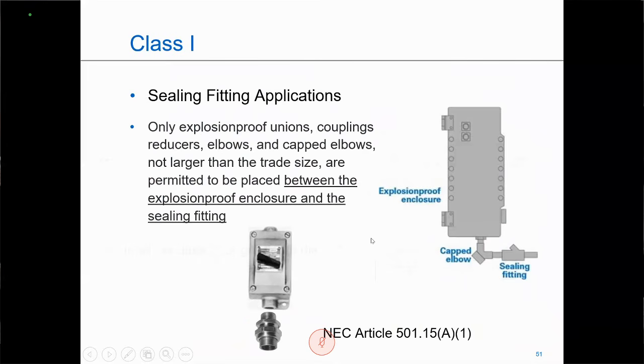So in this particular scenario, the union is very, very popular because it facilitates repair and replacement of the electrical equipment, especially when it comes to instrumentation. Instrumentation seems to need to be repaired quite often. So in this particular scenario, if you have the union, which is really the three-piece coupling for hazardous location, you just simply undo your conductors, unscrew the three-piece coupling, take the device off, repair or replace it, bring it back, and just rescrew the three-piece coupling together.